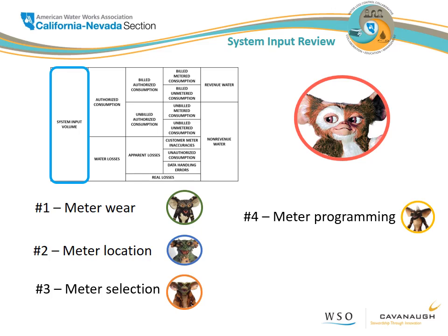This is where the conversion may occur, and perhaps it's converted from a pressure differential measurement into an electronic signal, and it's put on a 4 to 20 milliamp range. Well, the settings for what constitutes 20 milliamps or maximum flow, those are settings that have to be programmed in.